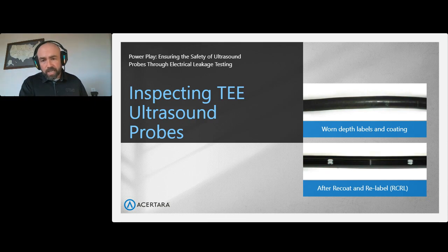What you see in the image below is that there are services out there that will do a recoat and relabel on those. They put new depth markers on, and they put a new protective coating on to ensure that the probe is going to pass electrical leakage. It can resolve some of the holes and other issues that could have come up with that insertion tube. They're going to put a new articulation sleeve on it and make sure that the tip is polished. It looks really nice. There's not going to be tooth drags and all those kinds of things. That's certainly possible. So there's remediation possible if you pay attention to these things and get them back to a service provider when you find them.